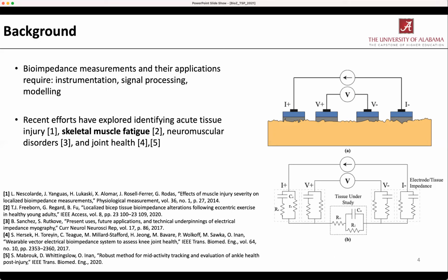And now, instead of interfacing to conductors and wires, we are interfacing to a biological tissue. So we have the contributions of that interface. What does an electrode connecting to skin look like? What are the charge carriers? What impedance does that introduce? It's no longer a near perfect conductor that can be thought of as only a resistor. So what does that change? What do we need to accommodate in the design of that instrumentation?